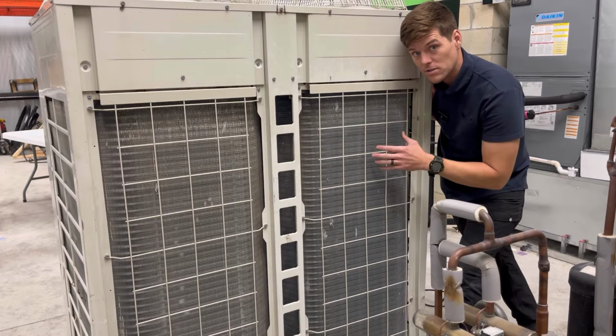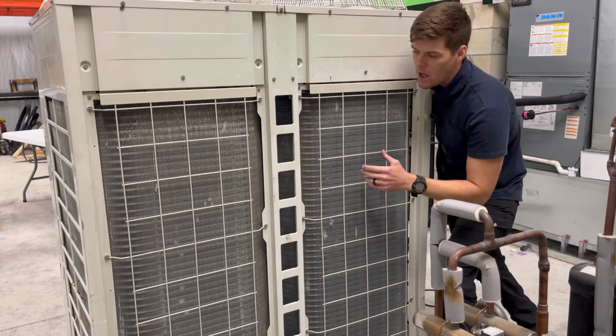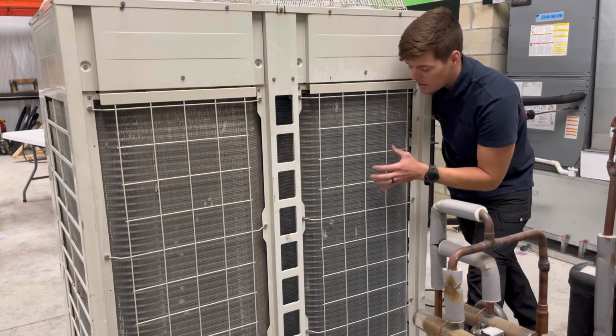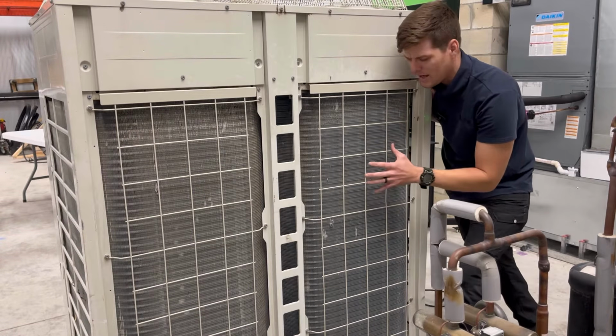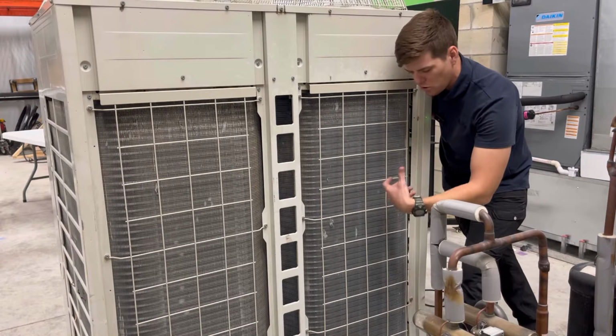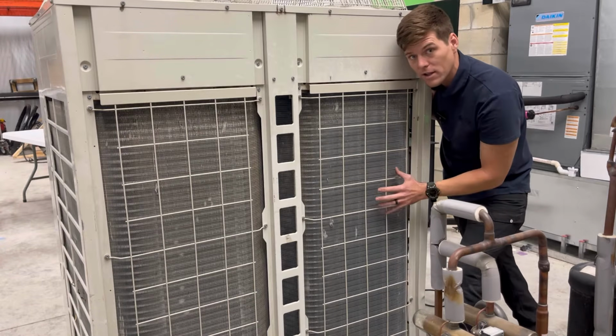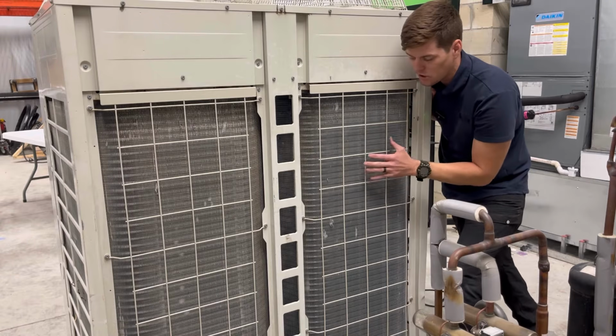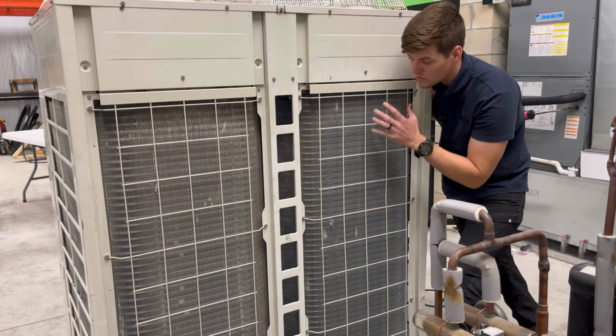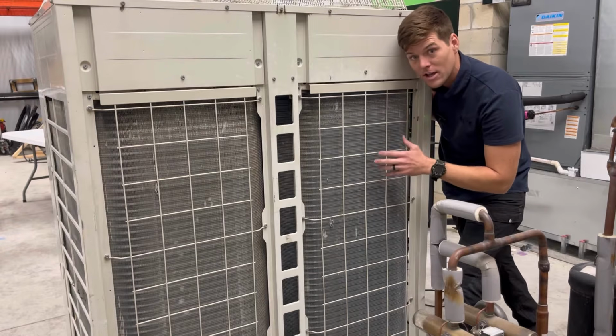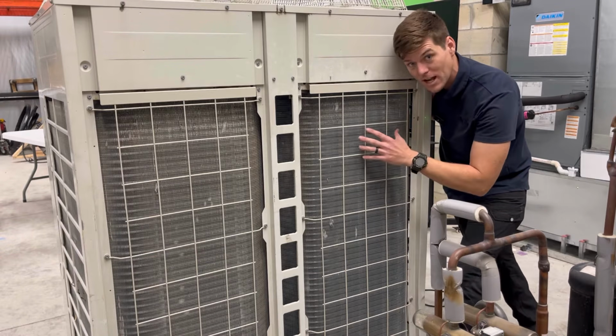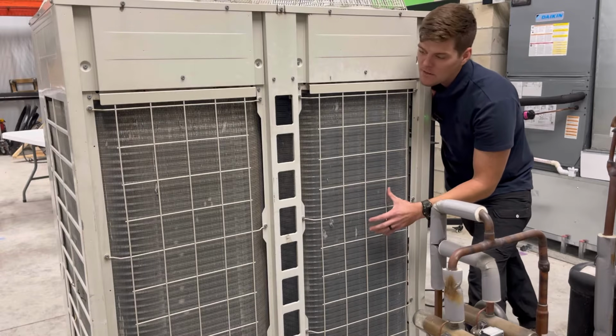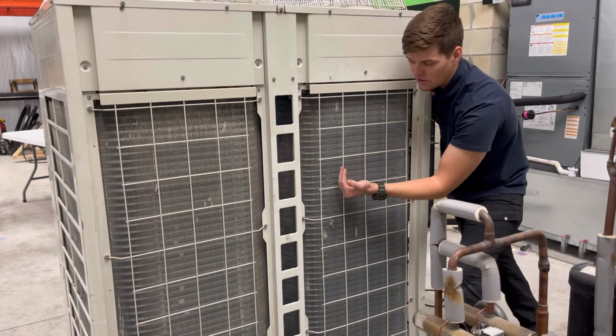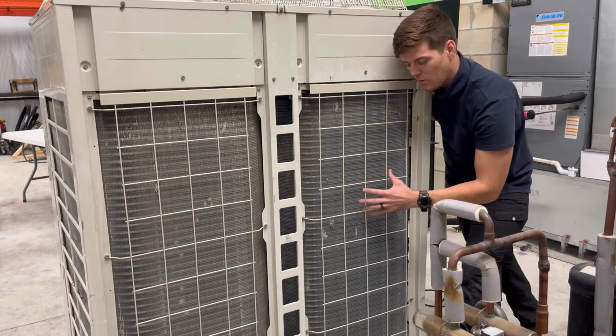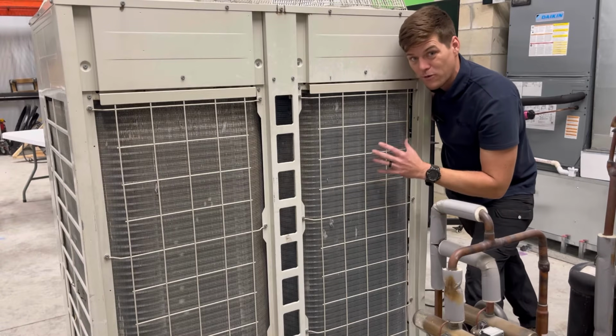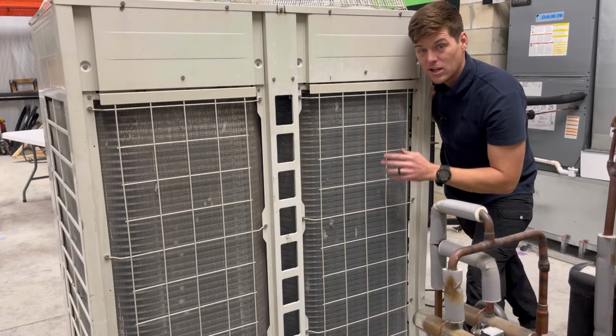A dead giveaway on an old system, especially a system with a bad four-way valve, is one of these coils would not look like the other, right? This one here on the right-hand side may be black, may be covered in green mildew and mold and all sorts of algae growing on the coil itself because, again, it never shifts over. It's always stuck in an evaporative state. This coil will sweat and sweat and sweat all summer long to the point where it's so cold and wet all the time that it starts to grow things on the coil. And so two different noticeable colors on the coil, one being light like this and one being extremely dark, is a dead giveaway that a four-way valve has failed and is not shifting. Look for it out in the field.